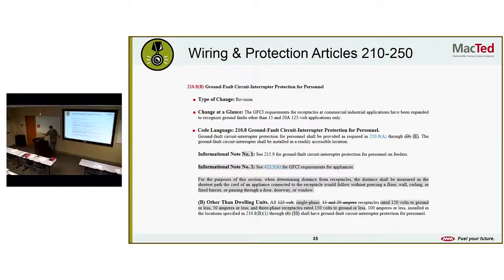Ground fault circuit interrupter, so GFI. Protection for personnel, they revised this. GFI requirement for receptacles at commercial industrial applications have been expanded to recognize ground faults other than 15 and 20 amp. If you've been following codes in the last few years, GFIs are almost required everywhere now. Used to just be in bathrooms, you know, we're used to seeing that where the places that there's water. Now it's damn near anywhere. And now they're expanding above your standard 15 and 20 amp as well. So instead of just your normal wall outlets, they're increasing that to probably welding gear and everything else that could shock somebody.